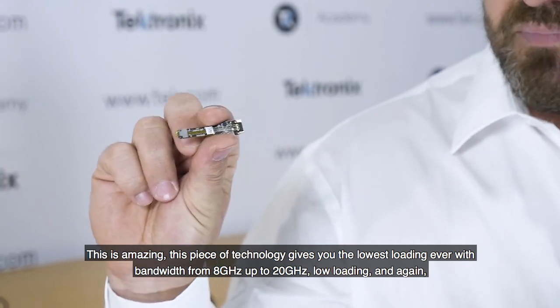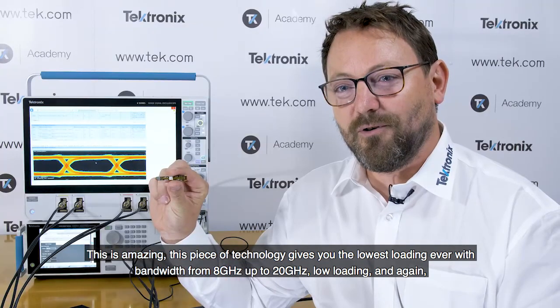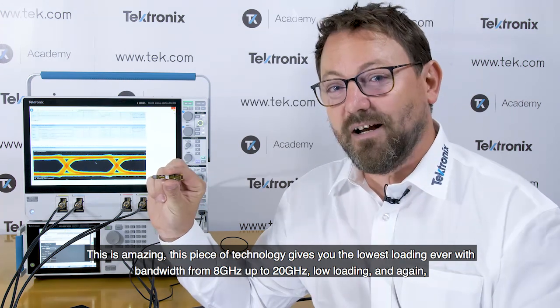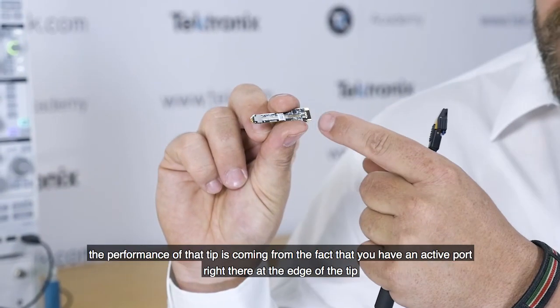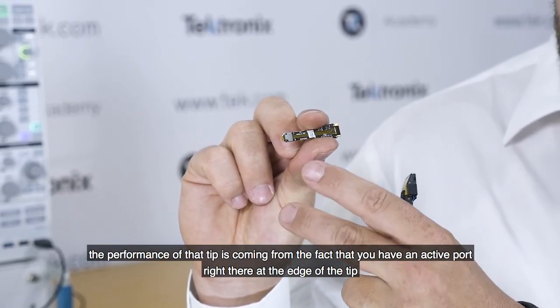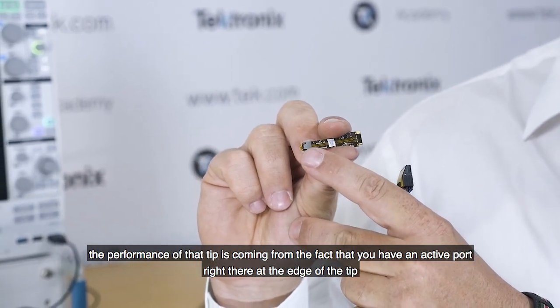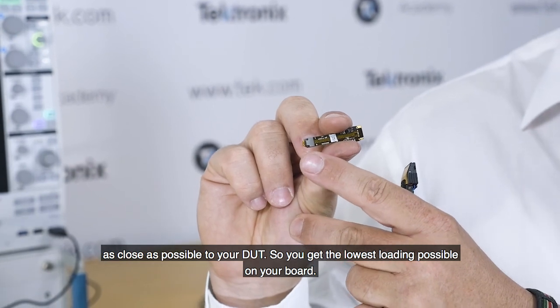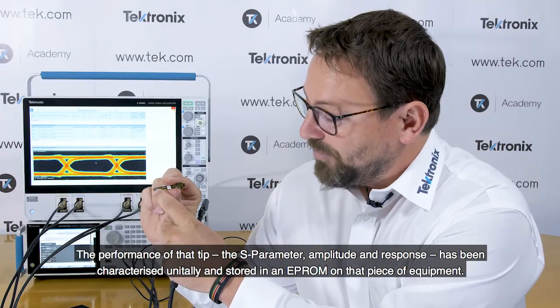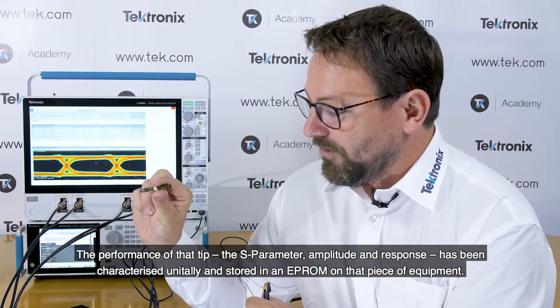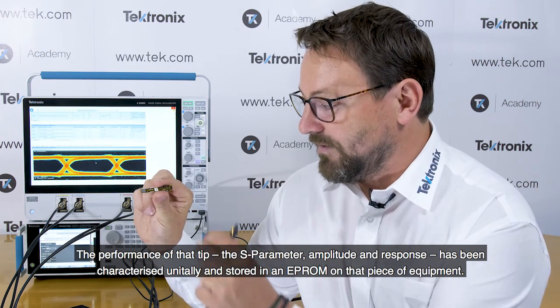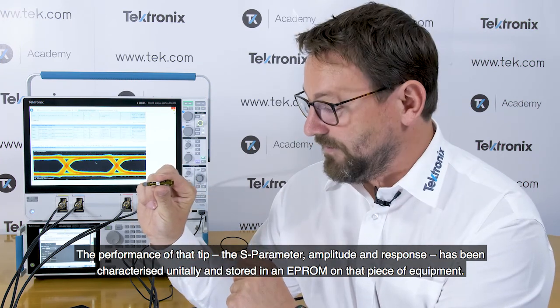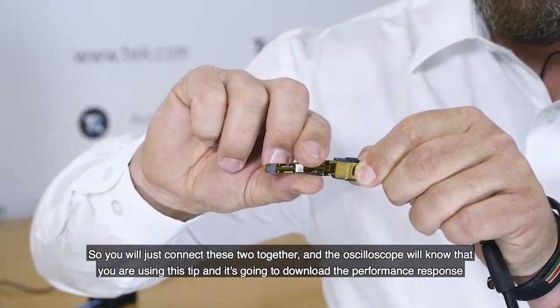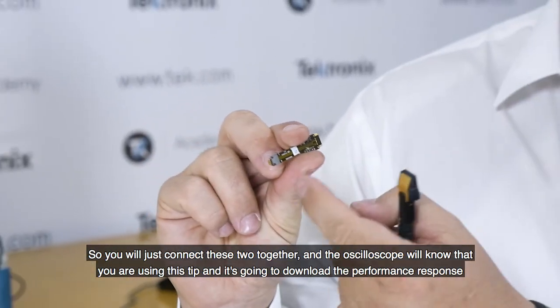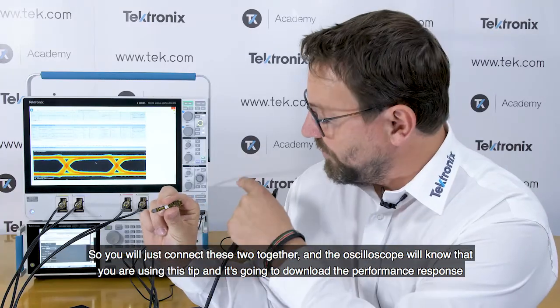This is amazing. That piece of technology gives you the lowest loading ever with bandwidth from 8 gig up to 20 gigahertz, low loading. And again, the performance of that tip is coming from the fact that you have an active part right there at the edge of the tip, the closest possible to your DUT. So you get the lowest loading possible on your board. The performance of that tip, again, the S parameter, amplitude and phase response, has been characterized unitarily and stored in an EEPROM on that piece of equipment. So you will just connect these two together, and again, the oscilloscope will know that you are using this tip and is going to download the performance response of that very tip and compensate for it.